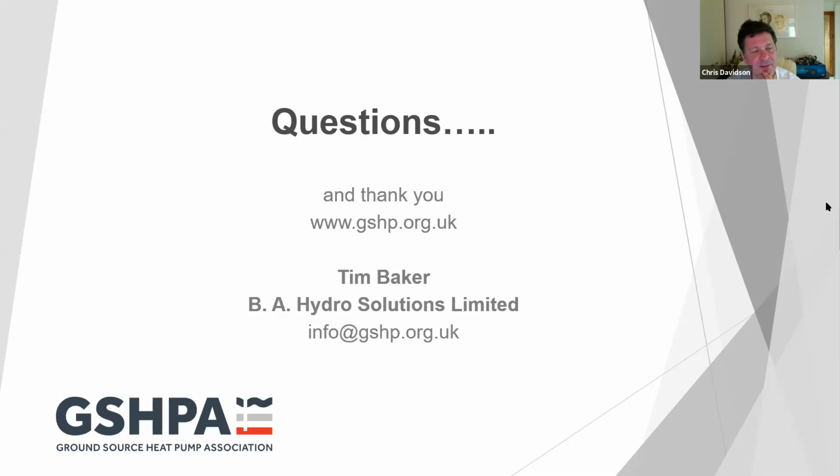I think the key point to bring out in what you're saying there, Tim, is even if it's a small system with one borehole, if you've got a serious problem with artesian water, and I'd plug, for those who haven't seen it, John Finlay's talk from last week, then one borehole's enough to get you in trouble. So I think it's a very important point that you assess the hydrogeological risks as part of any system of any size, really.